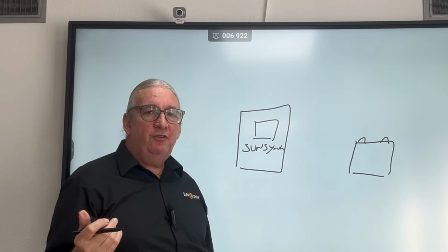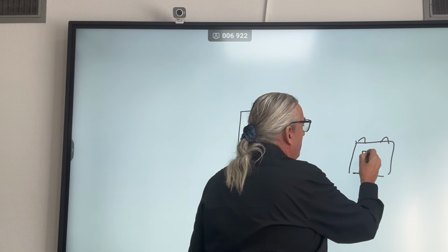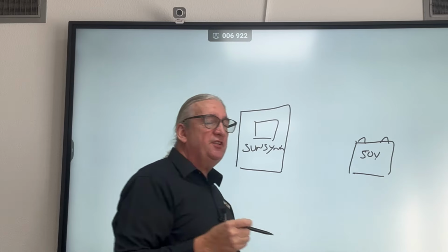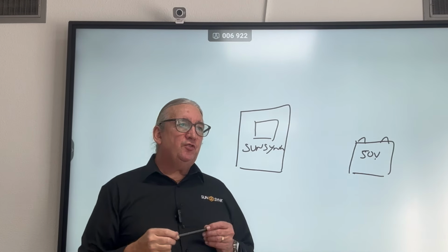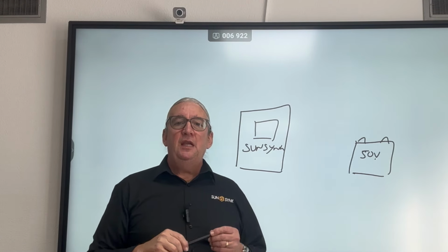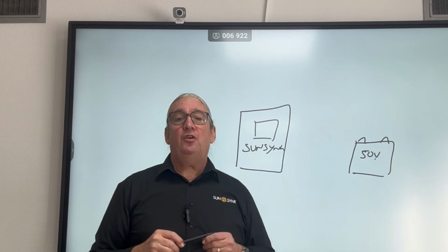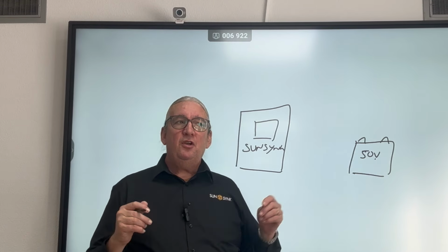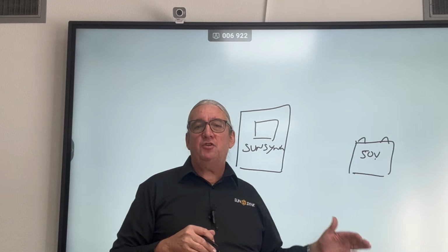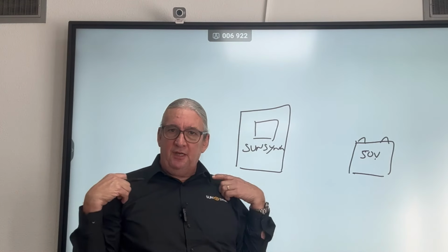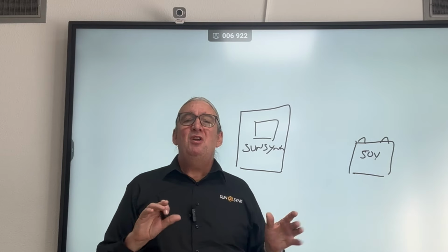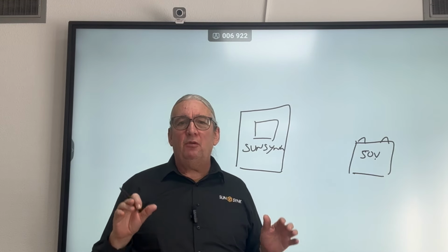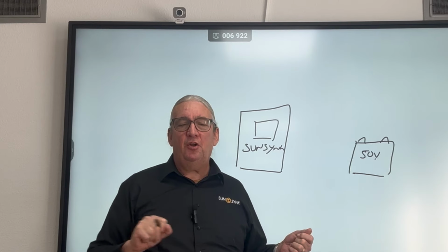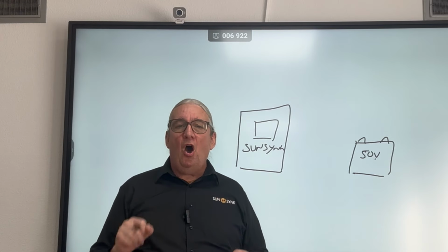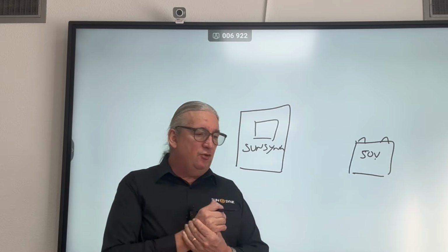Understand one thing about batteries. The most common battery voltage is around 50 volts. Why 50 volts? Because it's a safety threshold. 50 volts falls into a different directive. Below 50 volts is safe because you can touch it and you're not going to feel it. If there was a 100 volt battery and I touched across the terminals, I'd get a belt and it would hurt. At 50 volts, maybe if I'm super sensitive I might get a slight tingle, but it's not going to hurt me. Once you start moving upwards on the voltage, it becomes dangerous.